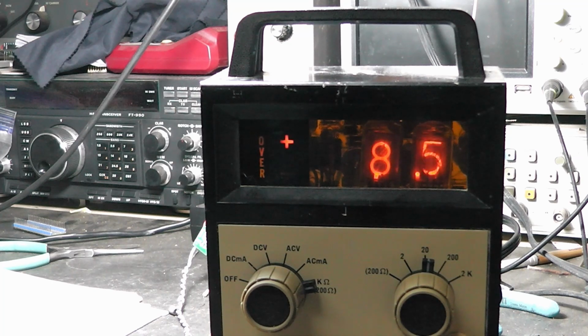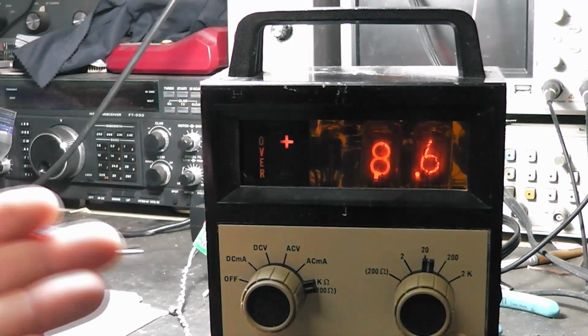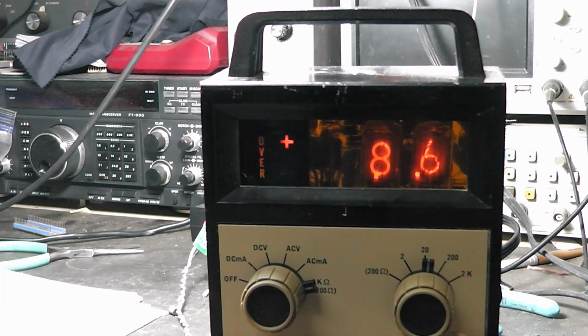If you are unable to obtain a reading of exactly over 0.85, obtain the nearest possible reading with the oscillator adjustment control. And it also mentions that it's going to change depending on your line voltage and stuff like that. So you may have to adjust it periodically, depending on if you move this around or whatever. Before you start, you take this somewhere and do some test measurements with it, besides your normal shop or your house or whatever. Flip this to here, and if this is reading way different than 0.85, then you may need to do some adjustments with it. What they're telling you, it's not going to be exactly as accurate, so you need to know that.